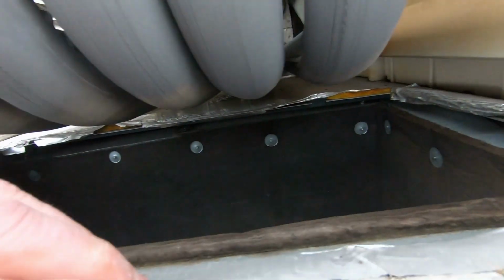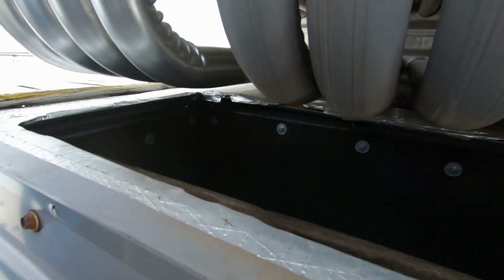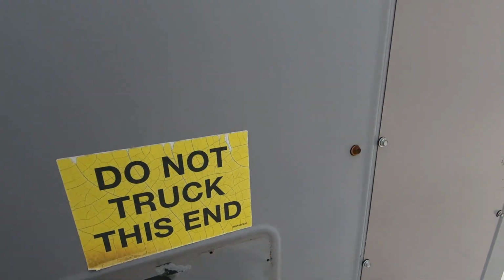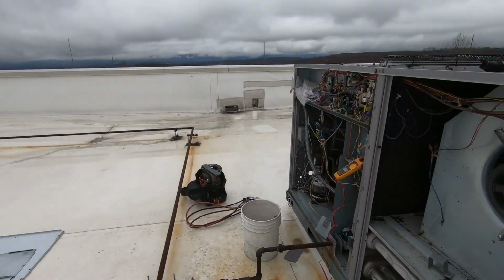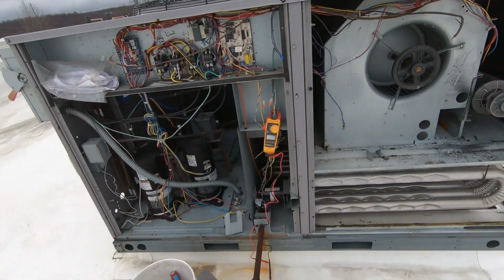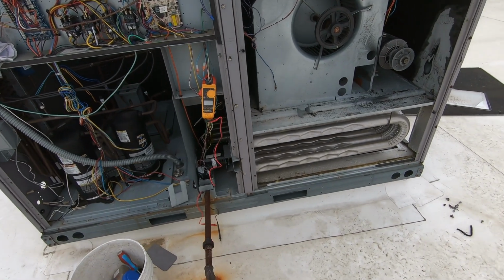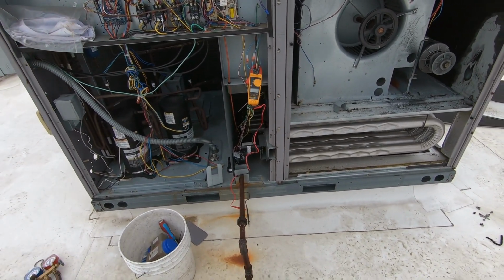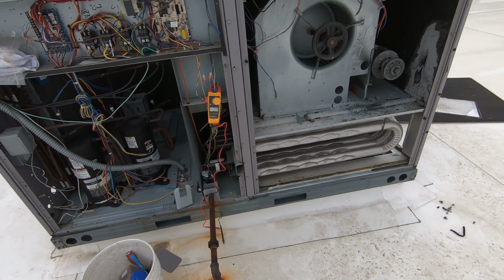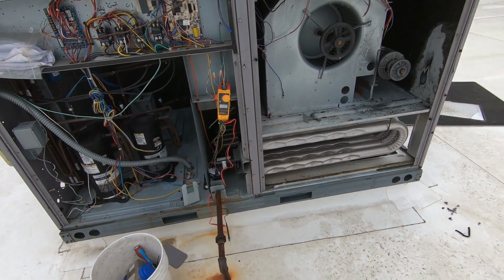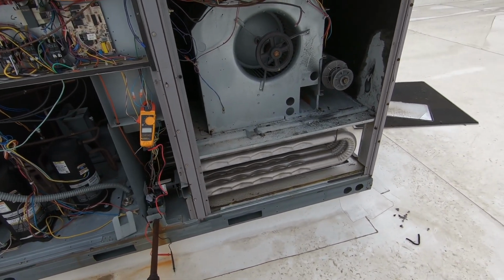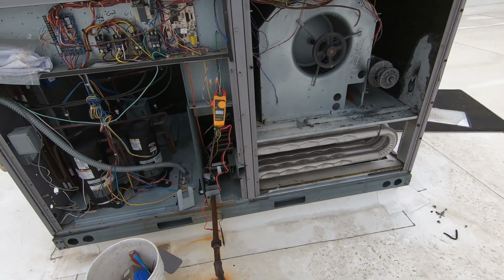Really lucky. And that's exactly why you never bypass a safety switch. Yeah, it's working fine when you bypass it, but once you throw a belt, or once a blower motor quits working, and this heat exchanger, that gas is just cooking in there. You've got to have air movement across it to keep it at a normal temperature. And with no limit, this thing could have been real bad.